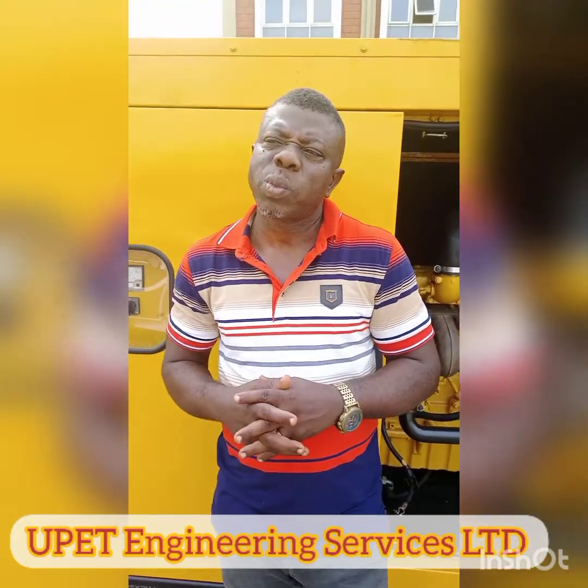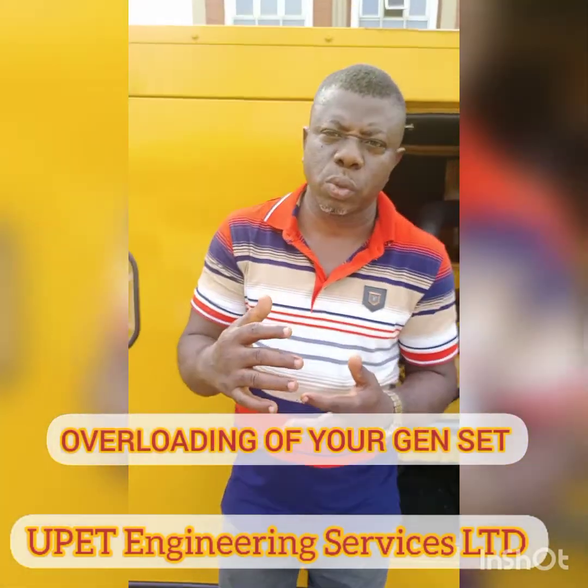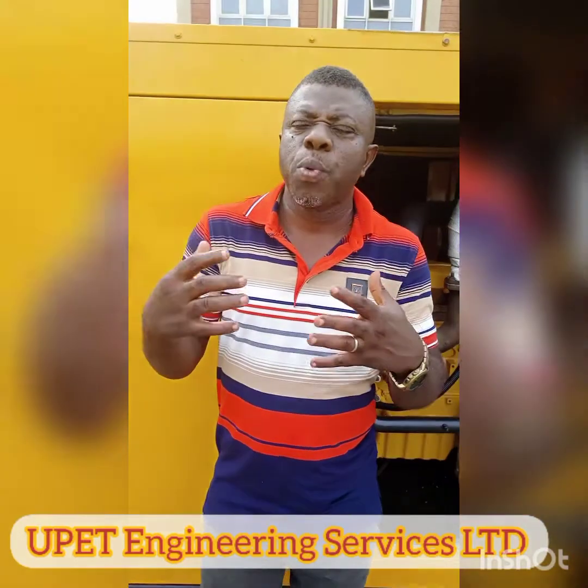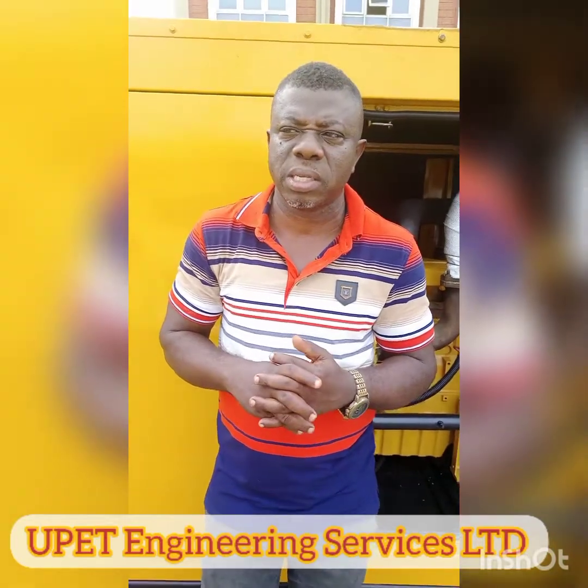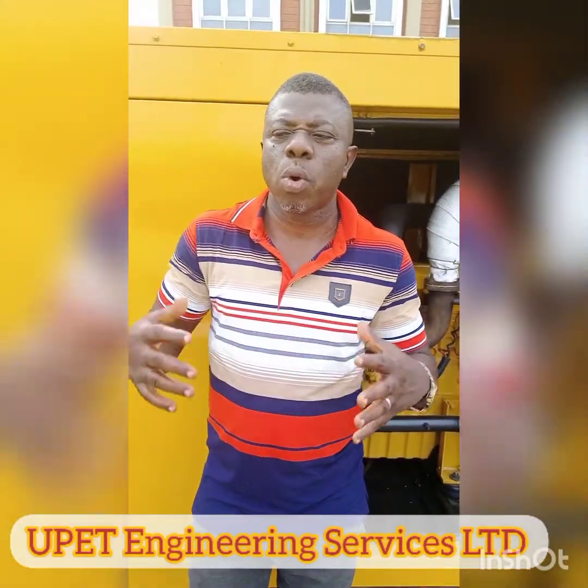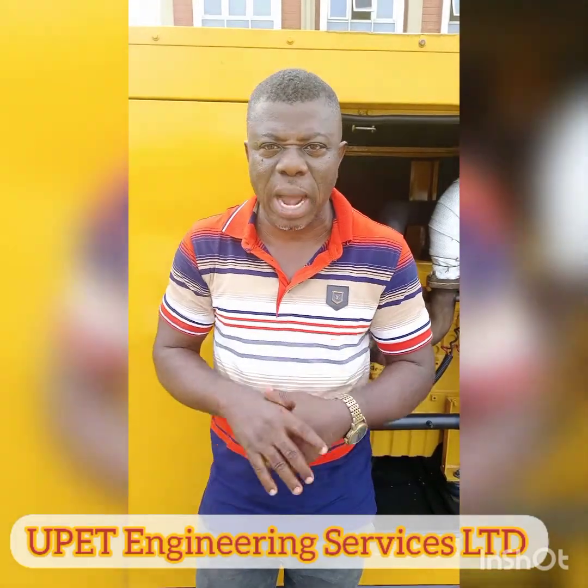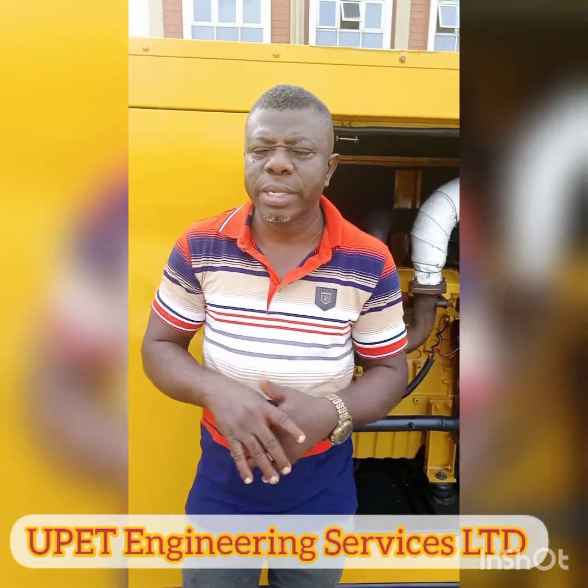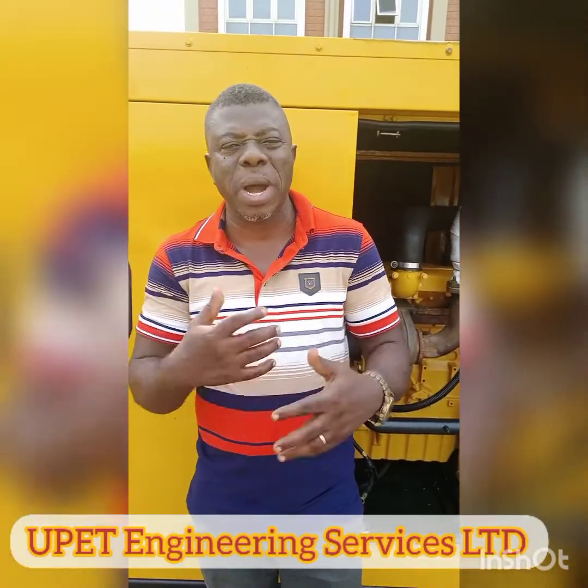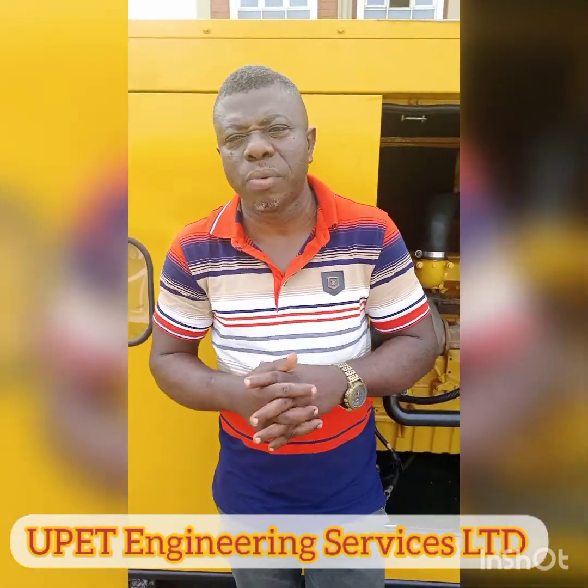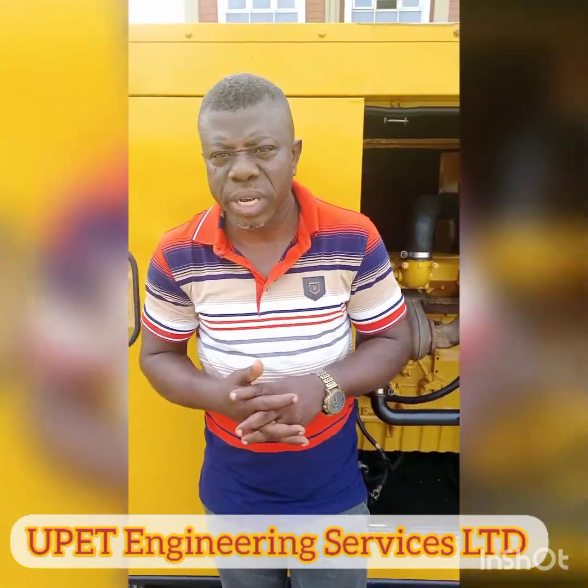And again, if your generator is being overutilized, that can lead to overheating. So what do I mean by that? Some people, the load they are carrying with their generator is higher than the capacity of that genset. So once that is in place, that generator will always be working under duress, and the result is that the temperature will always be high. So these are the things that can lead to overheating in diesel gensets. That is why whenever you want to buy a genset, you have to do a proper analysis of your load so that you don't overload your genset.